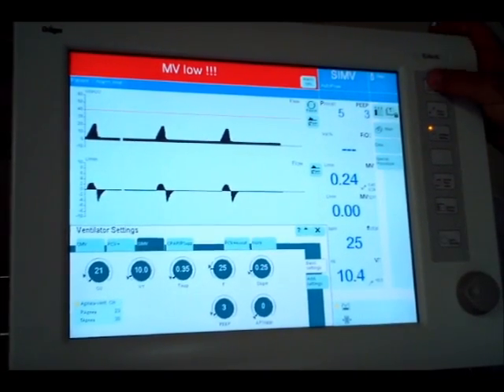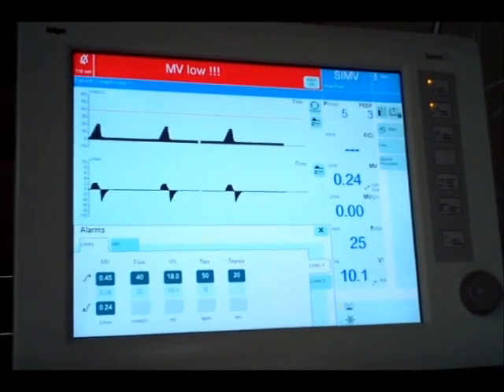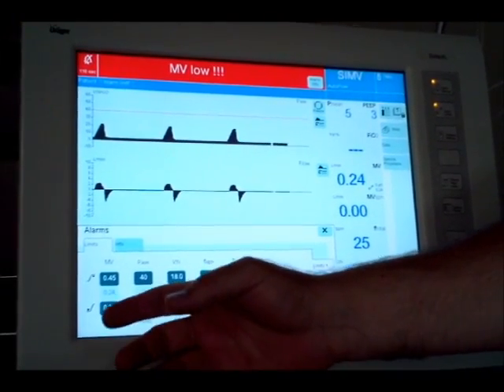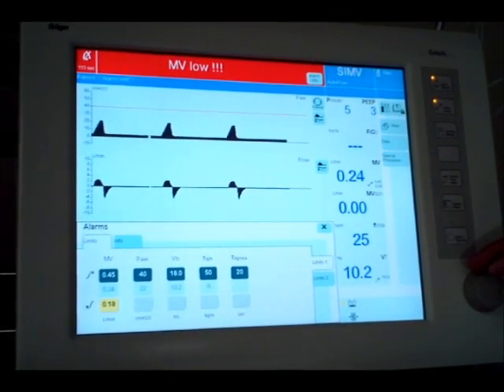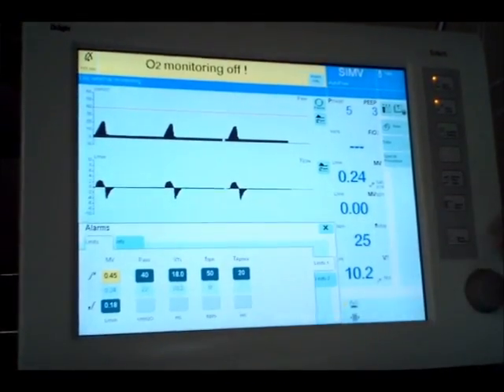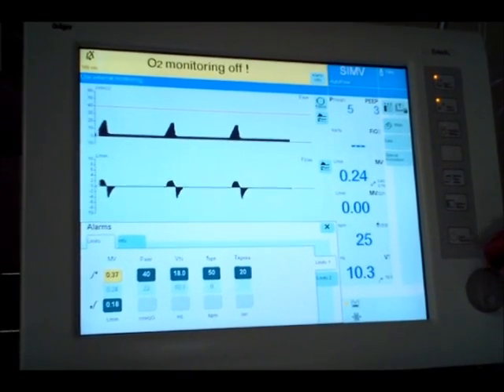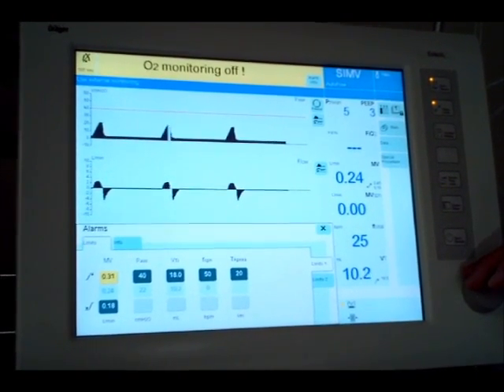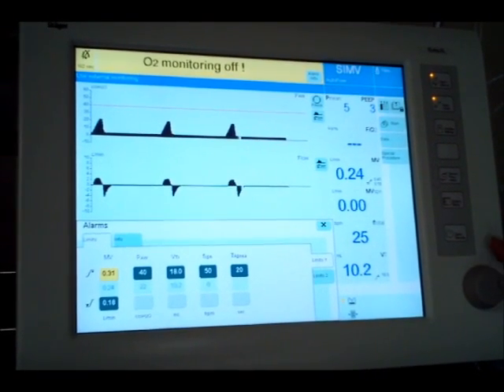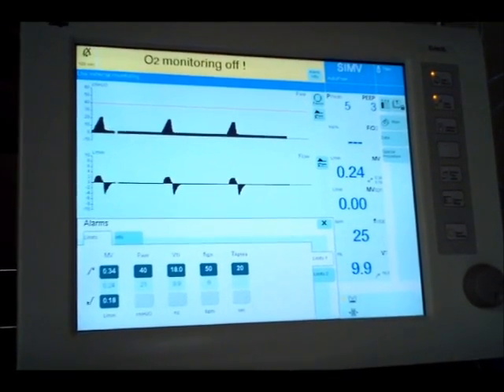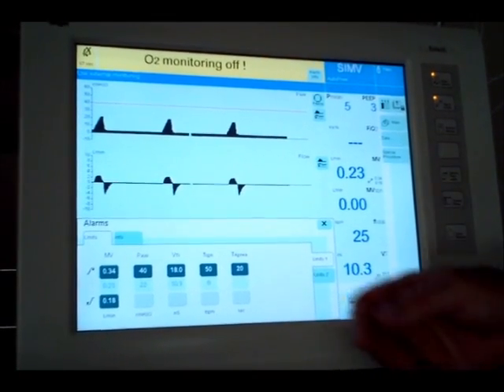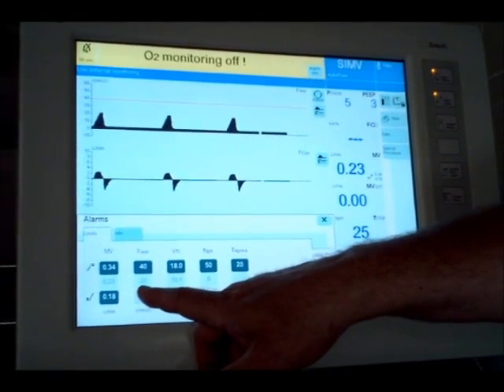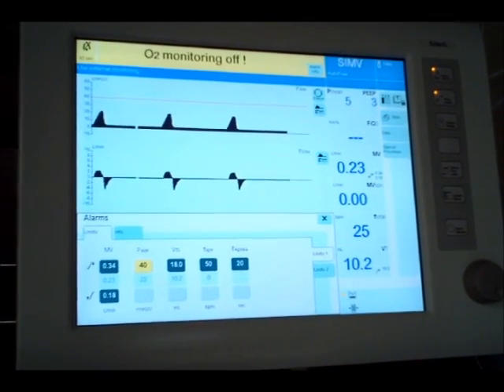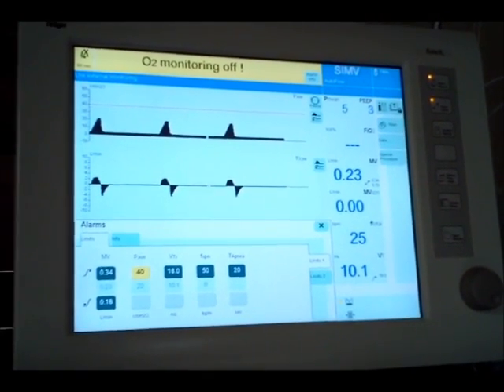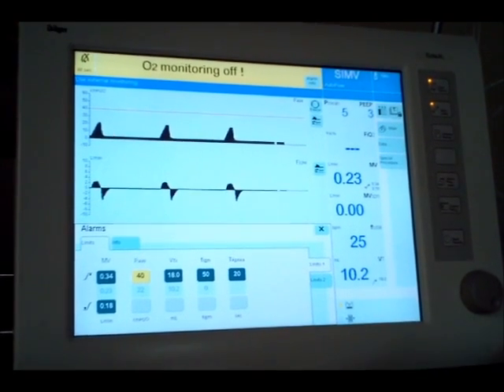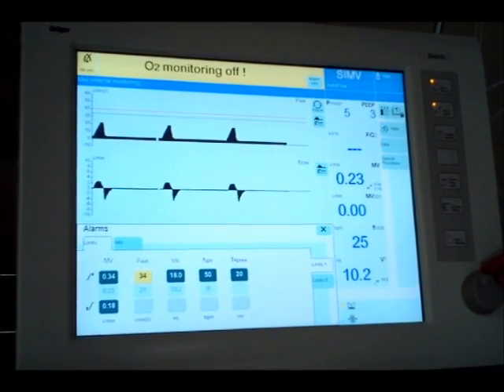All right. My ventilator conveniently is reminding me that I need to reset my alarms, okay? I'm right on this one, so I'm going to turn that down a little bit. And I'm not going to be too critical of where you set those numbers for now. If right now my minute volume exhaled is 0.24, if you set it at 5 liters, then that's probably a little too high. But okay, my PIP, or my peak airway pressure, is now down to 22. And we dropped our PEEP, and we dropped our tidal volume, so we dropped our peak airway pressure. Okay, that's fine. Sounds good to me.